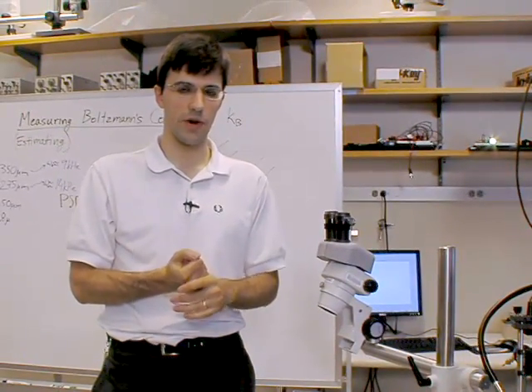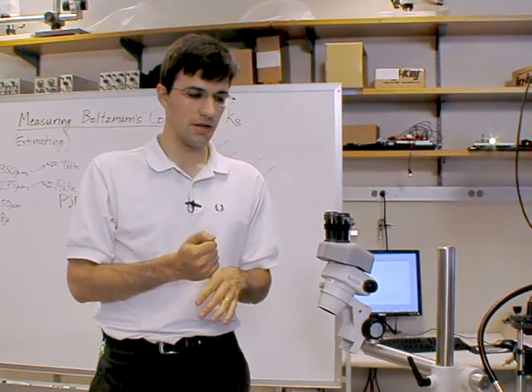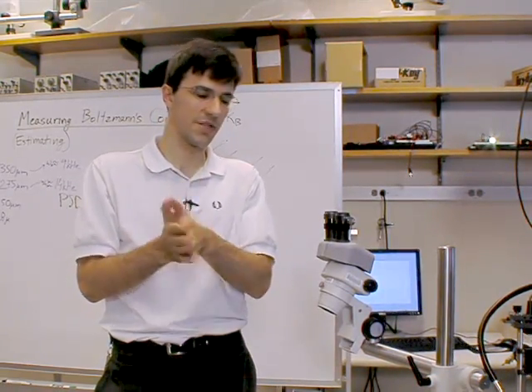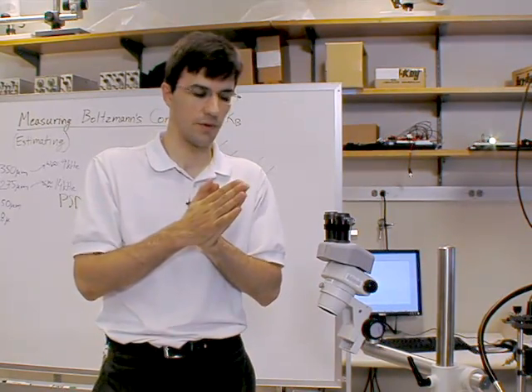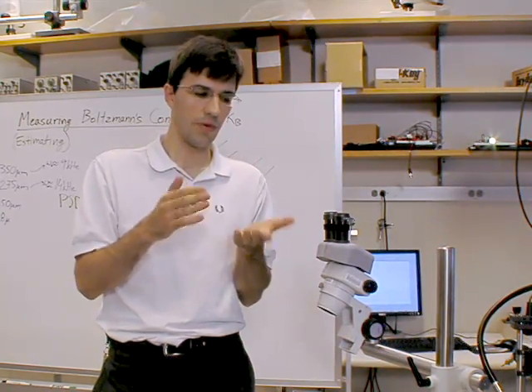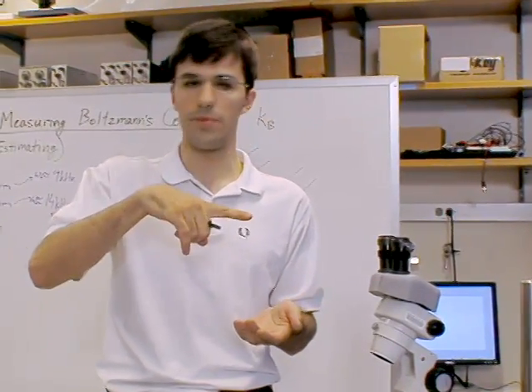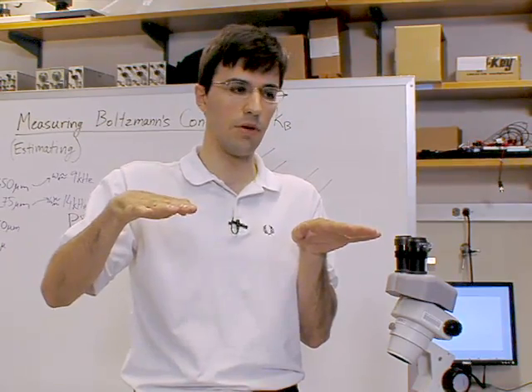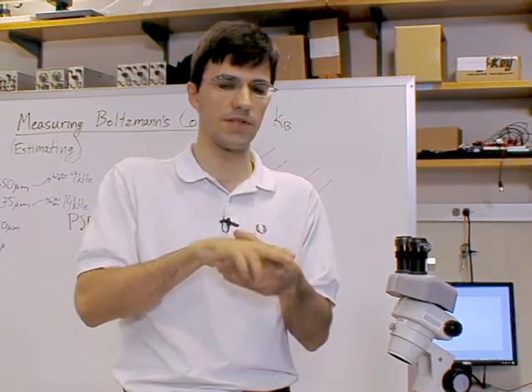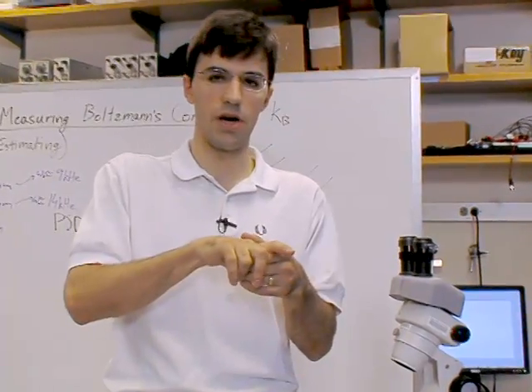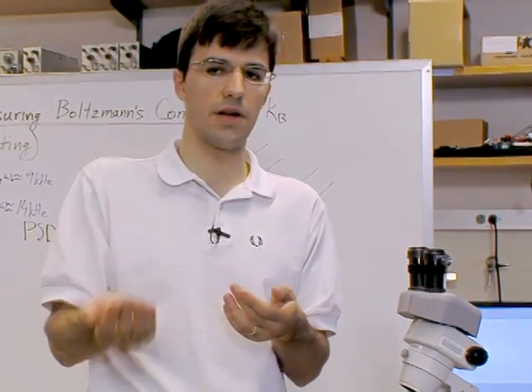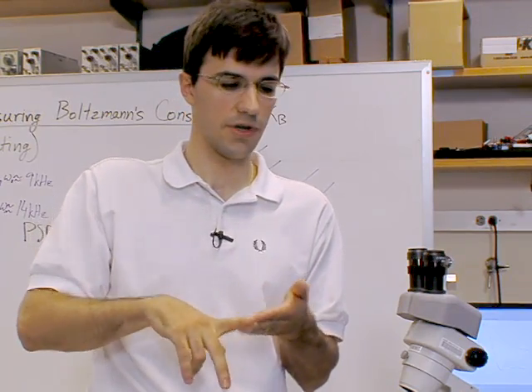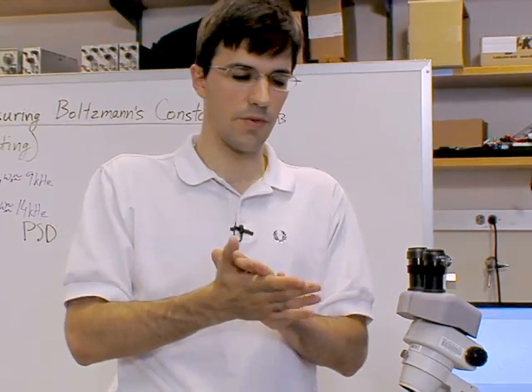I want to say a quick word about how to position your cantilevers to get the force curve that you want. When we were using the imaging cantilevers with the long middle beam, it's easy to just deflect that beam on its own and the side beams don't move. But now that we have two identical cantilevers for these measurements, you need to deflect one and leave the other one unbent so that it acts as a reference when you're doing your calibration and your force curves.